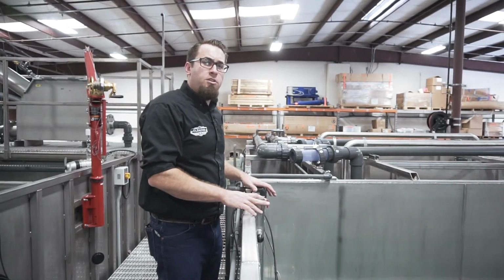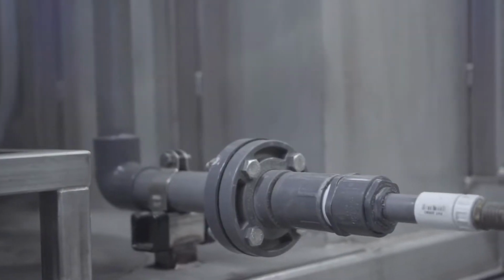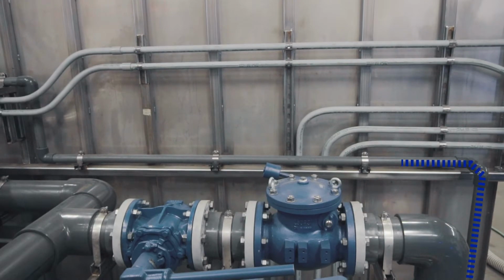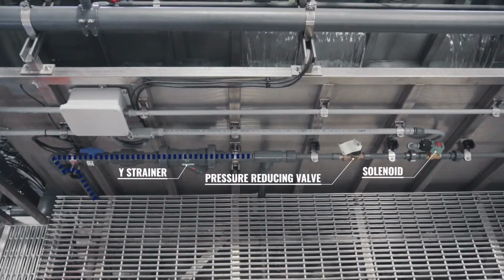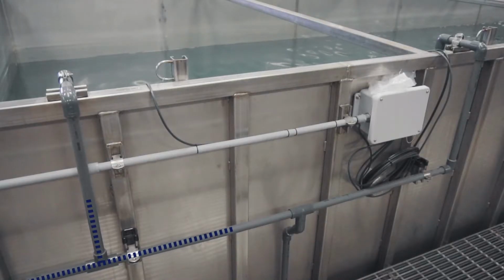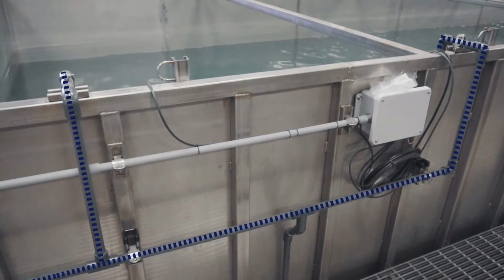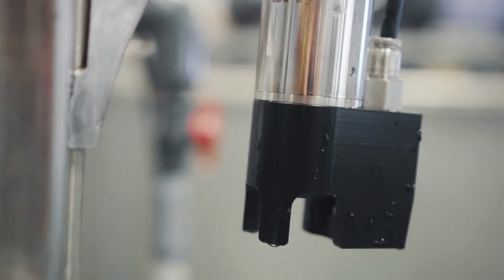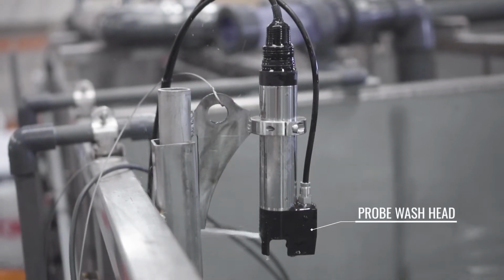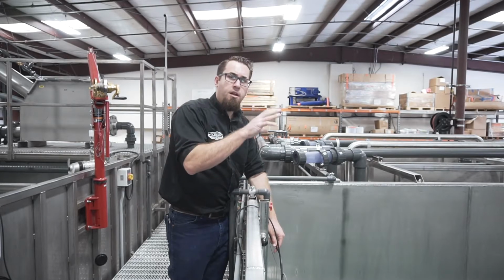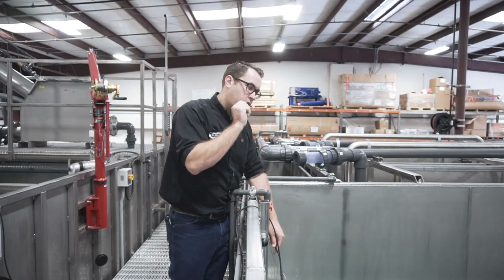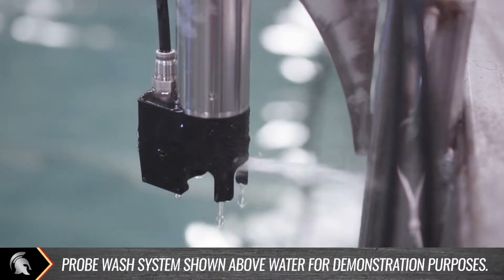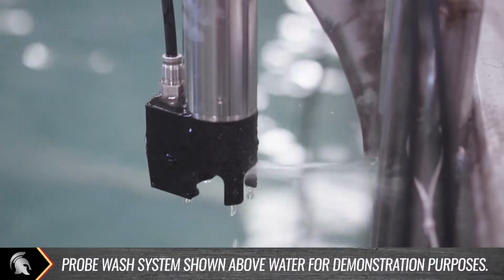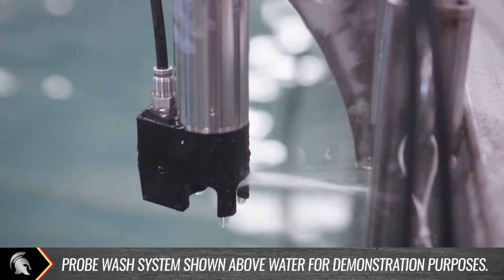The last feature of the Cloacina slide rail system and all of our sensory equipment that needs to be cleaned is the fact that we have a master probe wash system that runs throughout all of the treatment plant and goes to all of the individual pieces of equipment and supplies potable or reclaimed water to the probe head and periodically injects or bursts water across the face of it, thus cleaning the piece of equipment and extending out the actual maintenance interval for somebody to touch that piece of equipment.